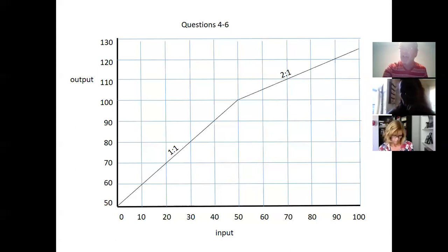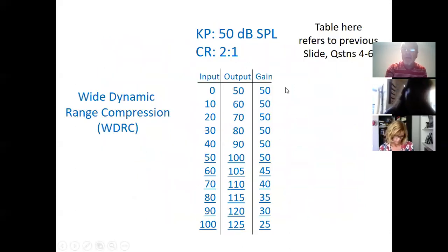Looking at the summary table, a moderate amount of gain, but read the maximum gain in this particular hearing aid. It's a weaker hearing aid. It's not meant to be powerful. It's meant for sensory hearing loss, outer hair cell pathology. It's the most common pathology, and WDRC is by far the most common compression. So it's reading its maximum gain, albeit not much, it's only 50, is being gradually reduced. See that?